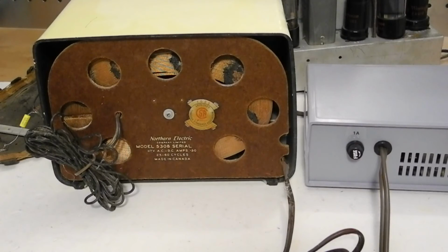The correct order of wiring the power circuitry should be AC line or live wire to fuse input, fuse output to on-off switch, switch to load, for example the power transformer or power supply circuitry, then the return from the load goes to the line cord neutral wire.